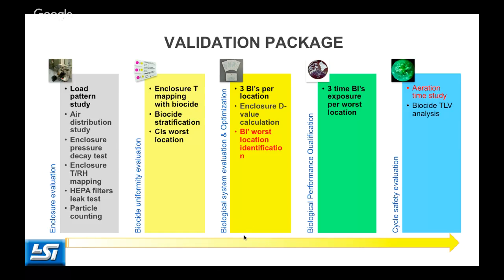At the end, after we have identified the worst location, we make the performance qualification with the BIs exposed 3 times in the worst location. And the system, if we succeed, the system is biologically validated. In the meantime, also we are making a study for the aeration, and also making biocide threshold limit value analysis.